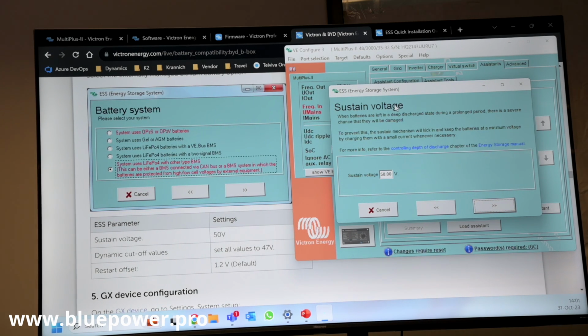Now we can see the sustain voltage. When the batteries are left in a deep discharge state for prolonged times - if your PV hasn't been producing for 2 weeks, or if you've got a backup system running ESS - you're going to wonder why the system only charges the battery to 50 volts. It's because you're running ESS on a backup system. But if you've got solar connected and it hasn't been producing for a week, it'll see the batteries sitting at 30% for a week, then apply the sustain voltage to the battery bank and thereafter charge the battery up 5% every day until PV production is recovered or the battery is up to 100%.